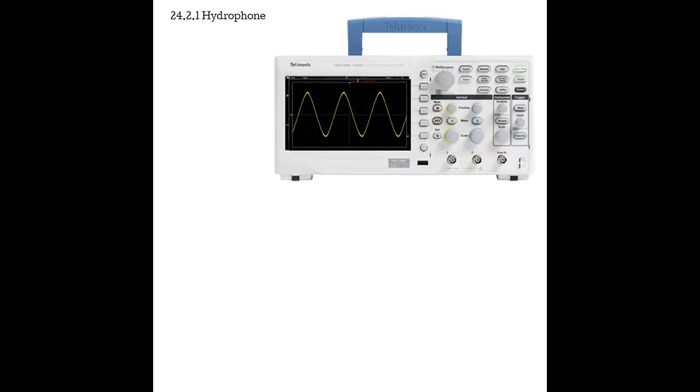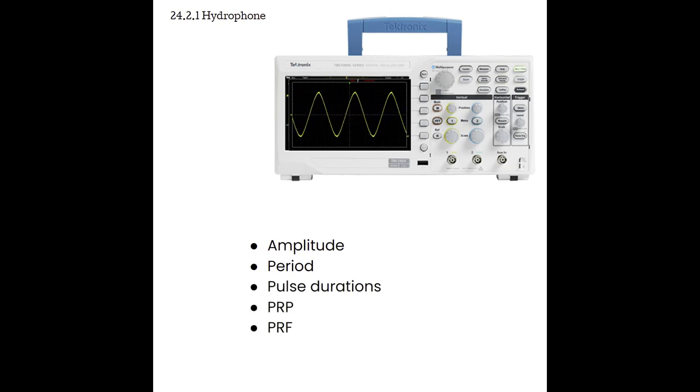When the probe is inserted into the beam path, the oscilloscope displays the information received by the PZT. So the hydrophone is actually able to detect quite a few things like amplitude, period, pulse durations, PRP, PRF, and the shape of the beam.